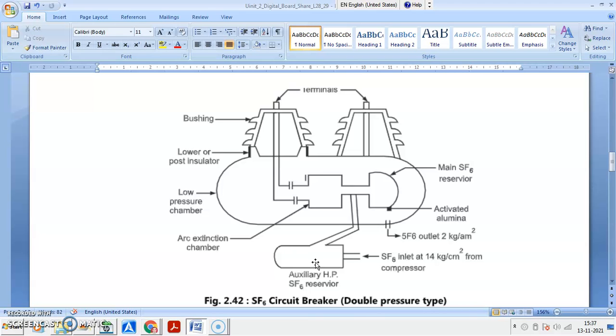So in this particular circuit breaker, gas follows closed path, as I told you. And activated alumina, which is Al2O3, aluminum and oxygen. These filters are used for gas filtration, which absorbs the arcing particles, carbon particles that get mixed with the gas, because this activated alumina filters out these particles. Then you are having the outlet gas, which you can directly feed to the compressor for increasing the pressure to compress it.